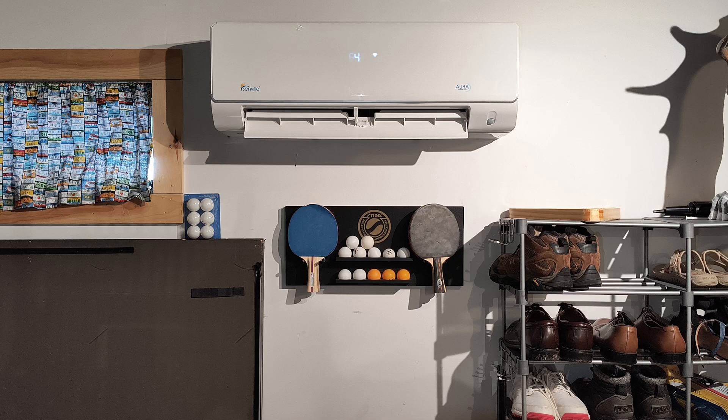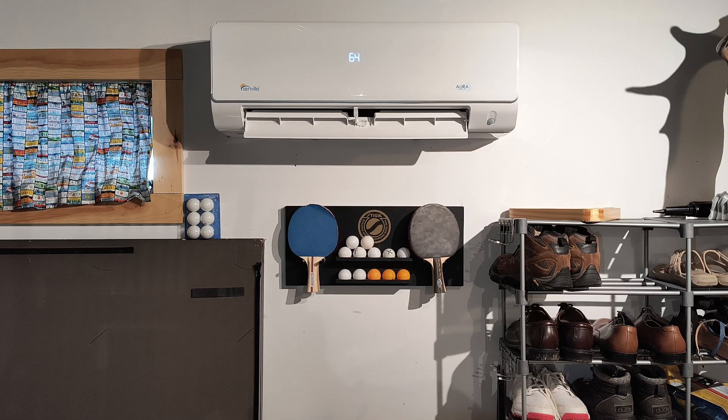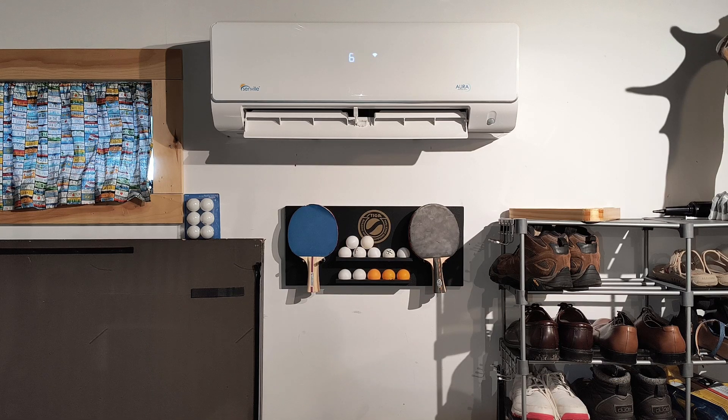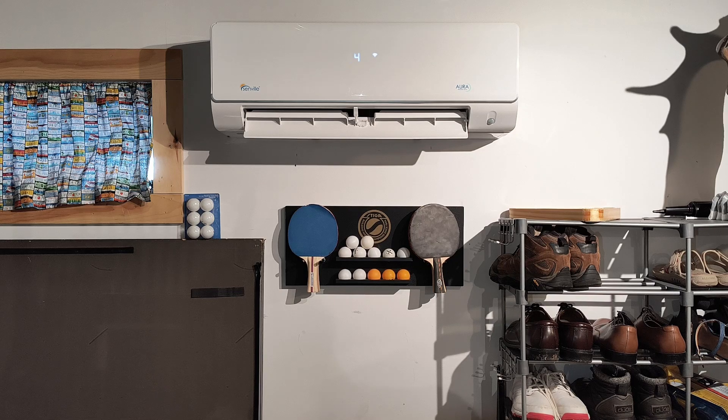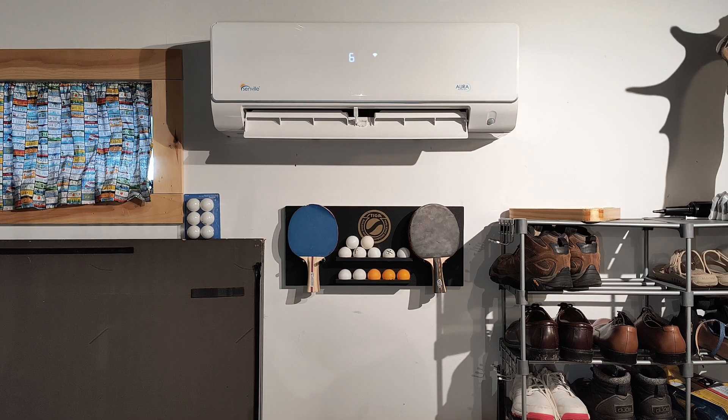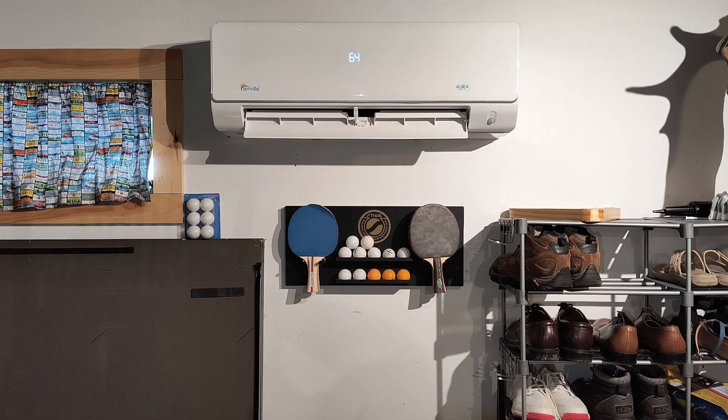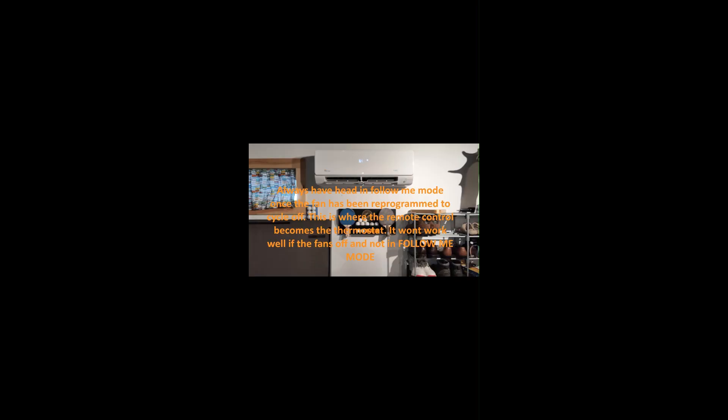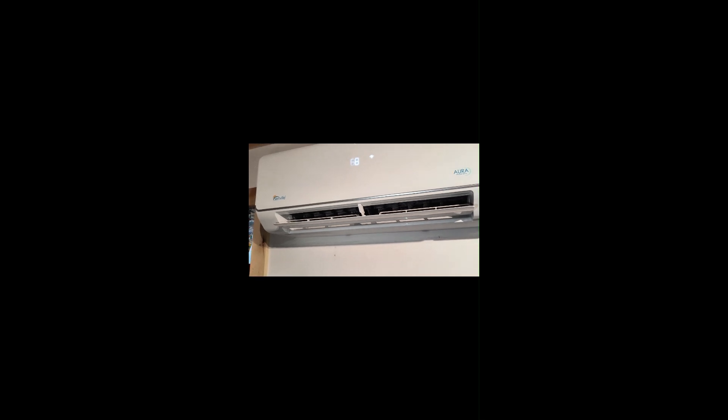So as we can see, the fan's still running, but once it stops, once it's reached set point, I'll go pan up in there to show you that it's still on but the fan is not running and just in sort of a standby. As we can see here, we've got a set point in the room temperature. It's actually above the set point by a few degrees. Yeah, and don't expect it to turn off immediately as soon as it hits that number. They always take a while. Give it 20 minutes. Sometimes they overshoot a few degrees by design.